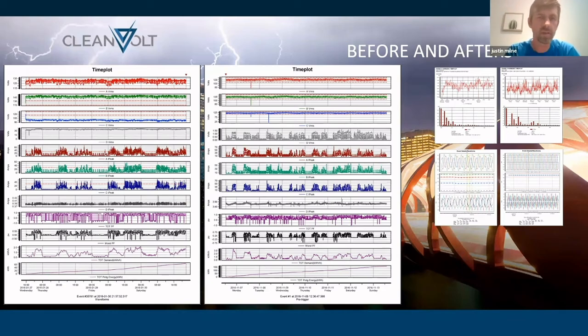As energy surges build in a system and create negative effects, with skin effect in the conductor, etc., and eddy currents start to build up in that conductor, blocking the natural flow of energy, it creates a lag between that current waveform and the voltage waveform. And the further the current gets from the voltage, the lower your power factor drops. So that's why it's very common to find people that have a calculated median of, say, 88 or 90 for their power factor, but they're operating in the low 80s. A lot of times, if there's no other reasoning for it, it's coming down to the energy surges and the negative impact that has on the system overall.